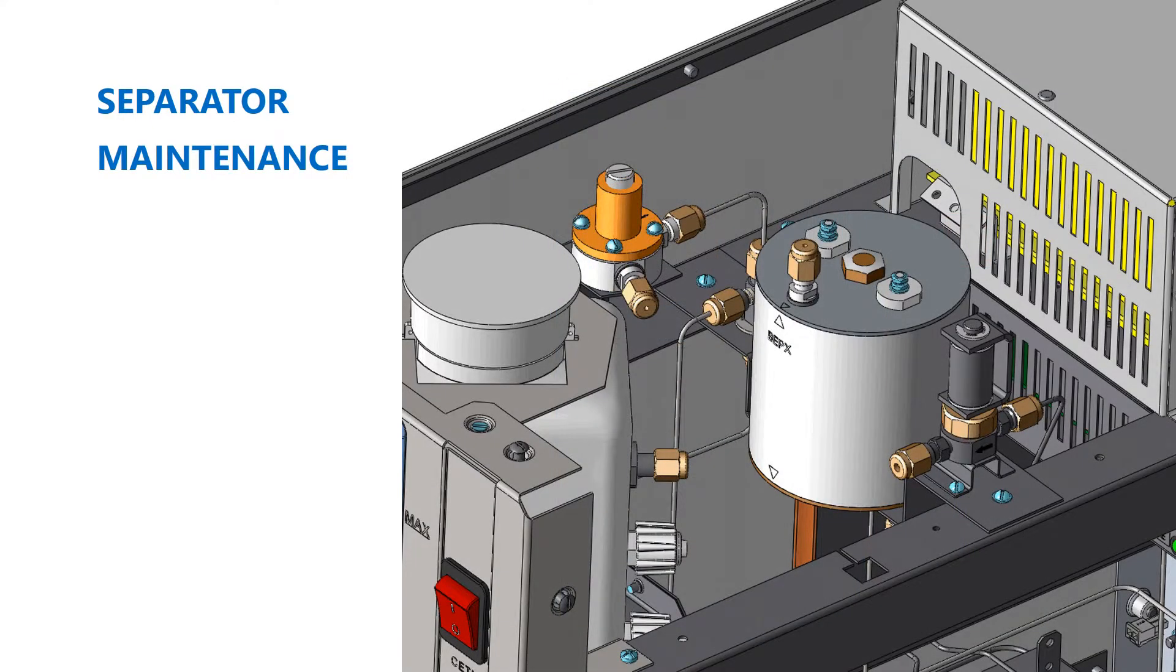If the red alarm indicator on the front panel is activated and a warning beep sounds while there is water in the tank, this means excess water in the separator or an accidental beep as indicated by separator sensors. The separator is a metal cylinder wherein hydrogen separates from water. There are two sensors inside, the long one and the short. They are separated from the body by fluoroplastic insulators. As soon as water level reaches the long sensor, the discharge valve opens and water flows into the tank because of small surplus pressure in the separator. At the same time, the valve clicking is heard, one click per second. If the water discharge valve is defective or the filter in front of the valve is clogged, water does not flow over and water level reaches the short sensor.